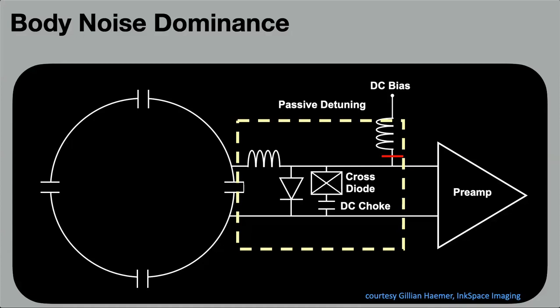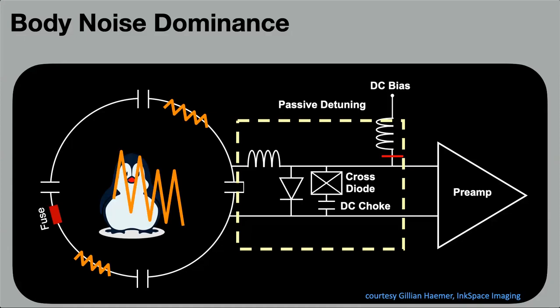Let's go back and talk a little bit about SNR again. We covered this in class a little bit. Now, copper is a great conductor. Replacing it with alternatives may increase the losses in the coils. So you can have some losses in the coil, but fortunately, the main source of noise in MRI actually comes from the subject. This gives you leeway to use new materials, which may be less conductive, without suffering image SNR loss. So even though this may be larger, if this is still dominant, that's not necessarily a problem. Now, since flexibility enables the coil elements to get closer to the body and improve SNR, any subtle loss that still can be seen maybe can be compensated by the proximity, hopefully, to the subject.